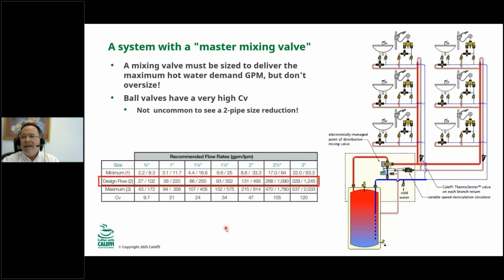Try and get total hot water GPM demand from the building. If it's a retrofit, that's hard. You just don't know, but at least try and estimate it. If you had a 50 room senior living center and you knew that each of the apartments might be using 2 or 3 GPM at the same time every day, then you can come up with an estimate of hot water that you need and try to do your best, or get the GPM load or the demand from a designer.